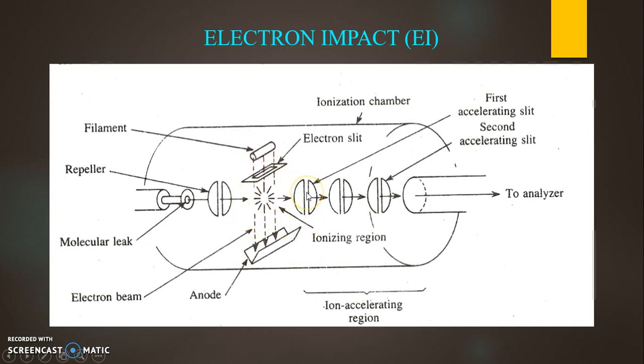This is the first accelerating slit and this is the second accelerating slit. From this the electrons or the ions will travel to the ionizer to the analyzer.